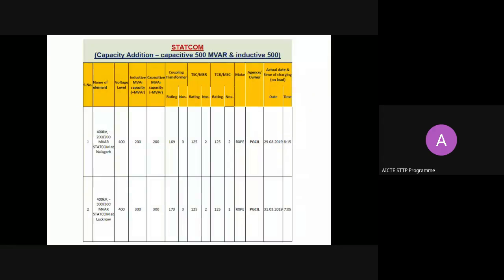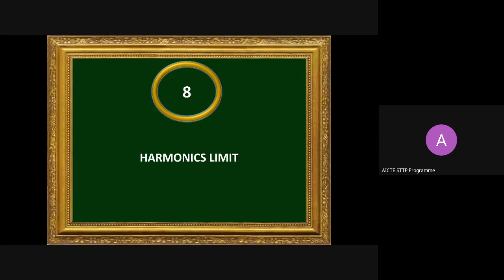For example, STATCOM: at the Power Grid Corporation substation in Lucknow, they have a 300 MVAR STATCOM at the voltage level of 400 kV. In earlier days there were no STATCOMs. Now static VAR compensators and STATCOMs are present on the power grid networks. Even for the local Tamil Nadu grid network, we are proposing to incorporate such STATCOMs at the 765 kV substation level. Okay, now we are coming to harmonic limits. How much is permitted? What to do if it increases beyond the permissible level? We will see one by one.